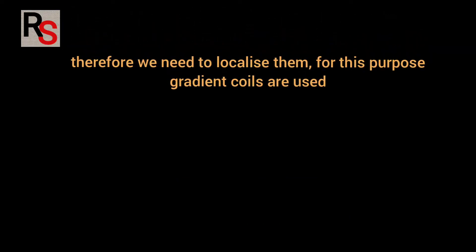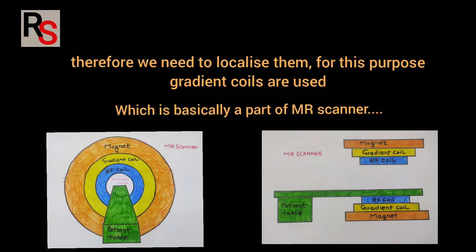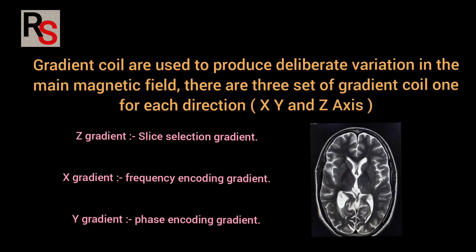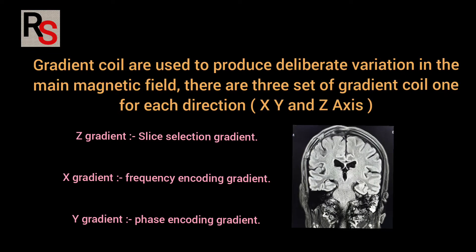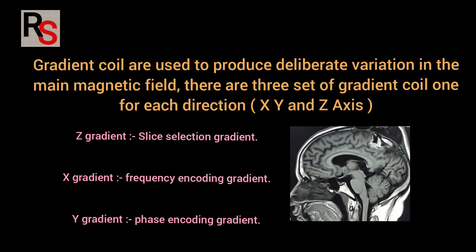For this purpose gradient coils are used, which is basically a part of MR scanner. Gradient coils are used to produce deliberate variation in the magnetic field. There are three sets of gradient coils, one for each direction: X, Y and Z.